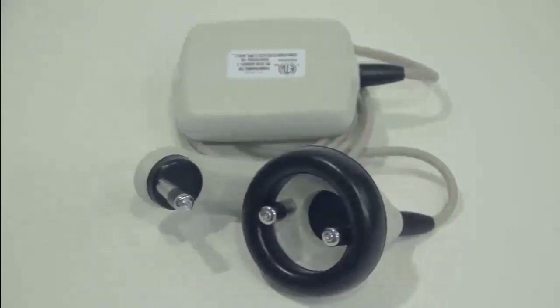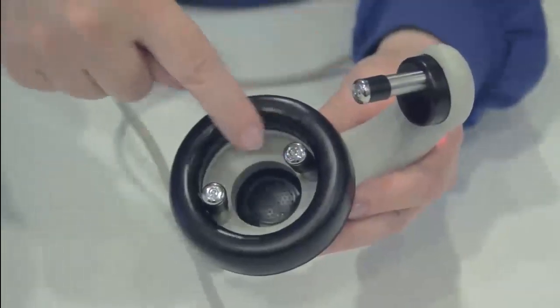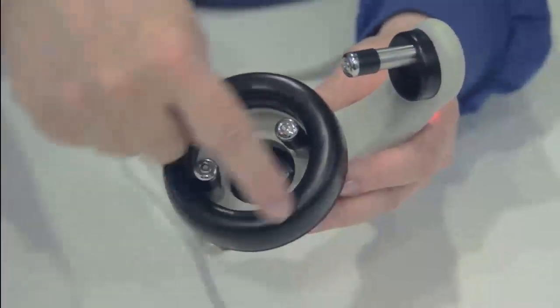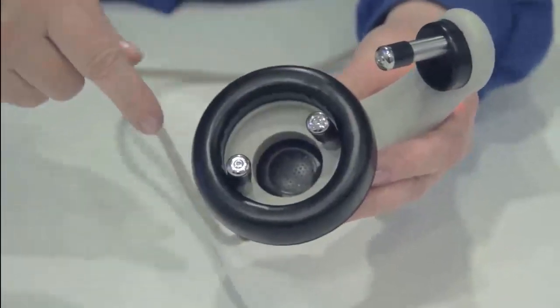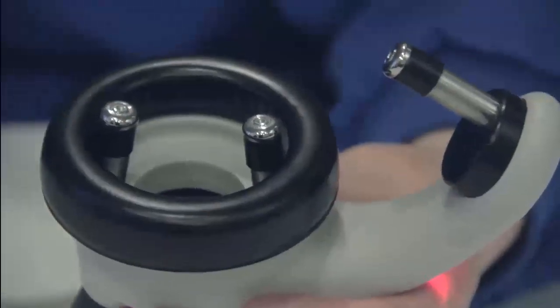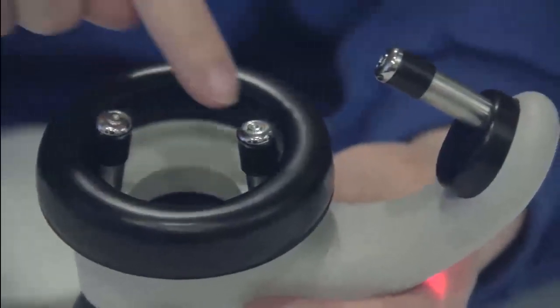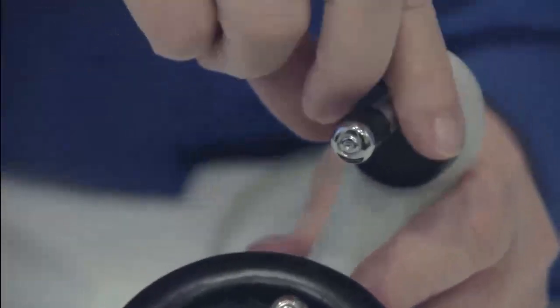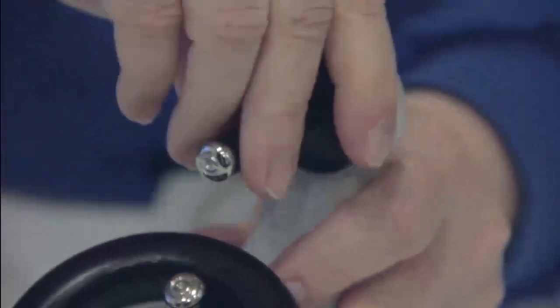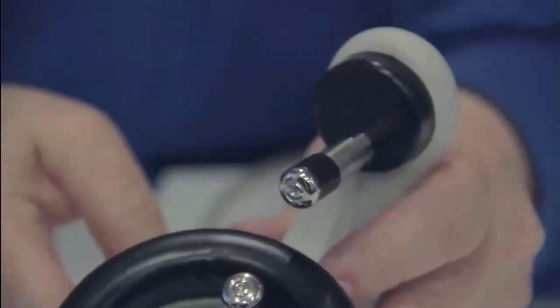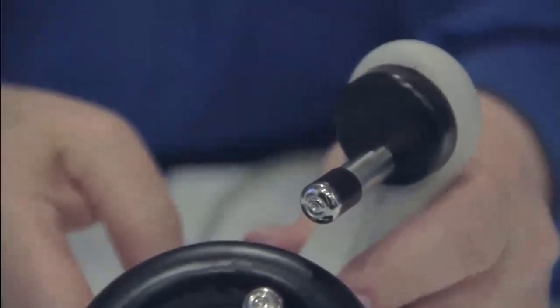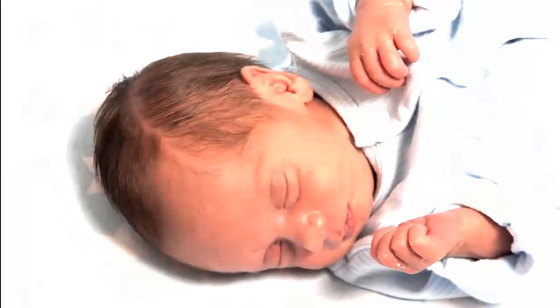The MB11 BERAphone includes 3 integrated, reusable electrodes and an ear cushion surrounding the acoustic transducer. The electrodes are mounted on a spring mechanism that allows them to conform to the shape of the baby's head. The vertex electrode is mounted on a disc that rotates 180 degrees to fit a wide range of head sizes. For smaller heads of premature babies, you may need to change this position. The BERAphone has been used successfully on babies as young as 32 weeks post-menstrual age.